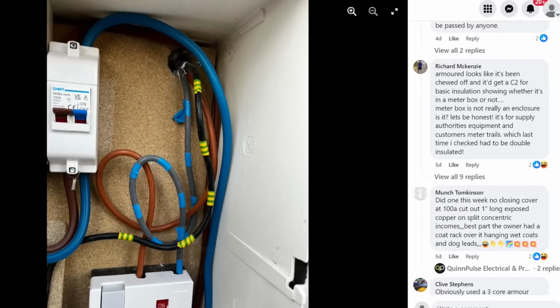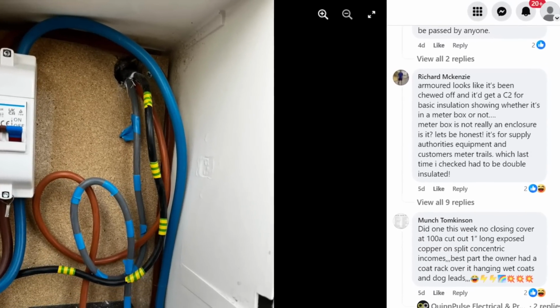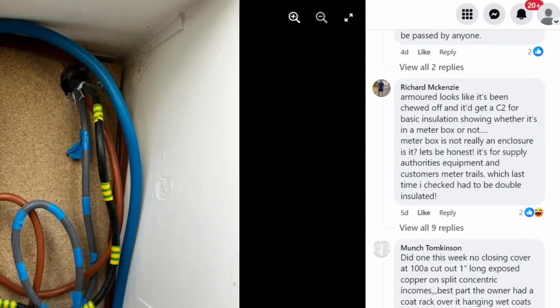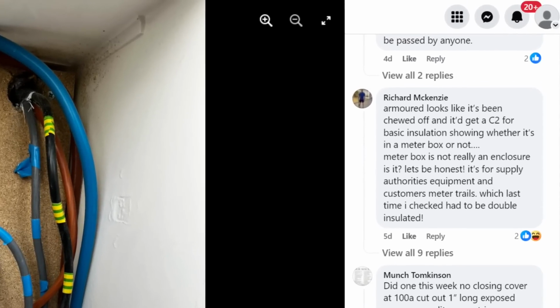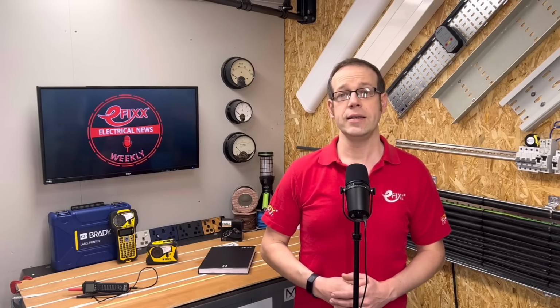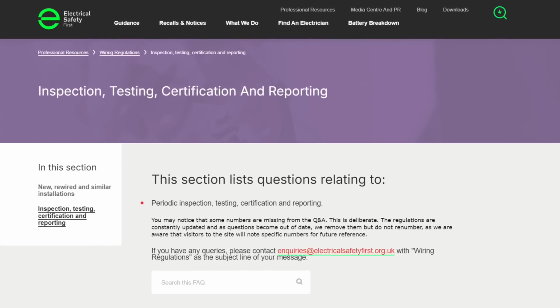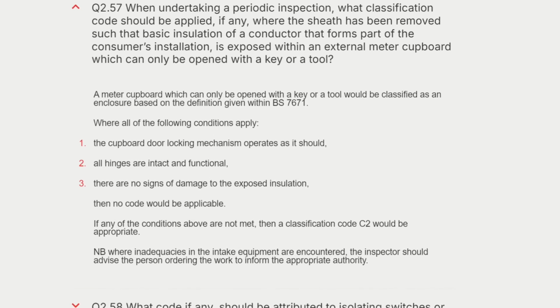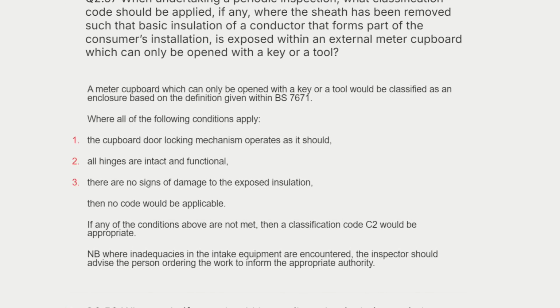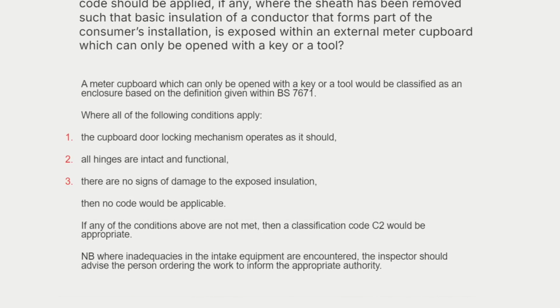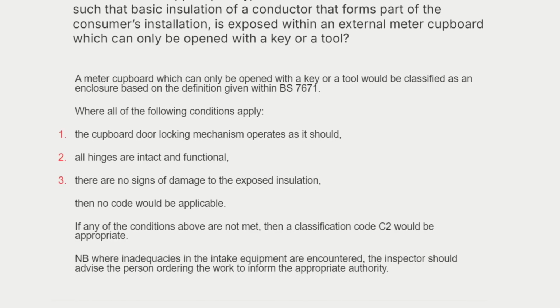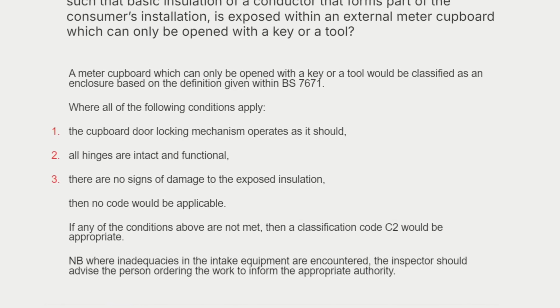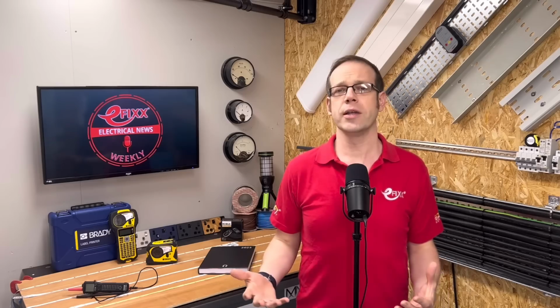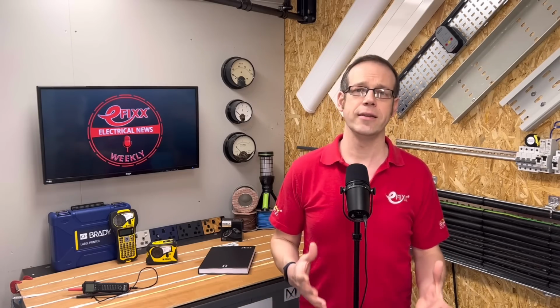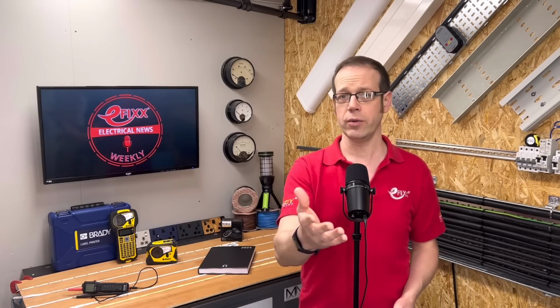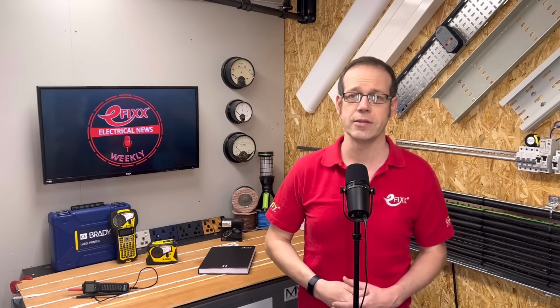In an EICR, many electricians would code the exposed single insulated cables as either a C3 or possibly C2 issue. But the Electrical Safety First charity disagrees. On its website it says that a meter cupboard which can only be opened with a key or a tool would be classified as an enclosure based on the definition in BS 7671. If the door lock and the hinges work and there's no signs of damage to the exposed insulation, then it's fine. Other organisations don't appear to offer the clarity that the trade requires. Let us know your view on conductors in meter cabinets in the comments below.